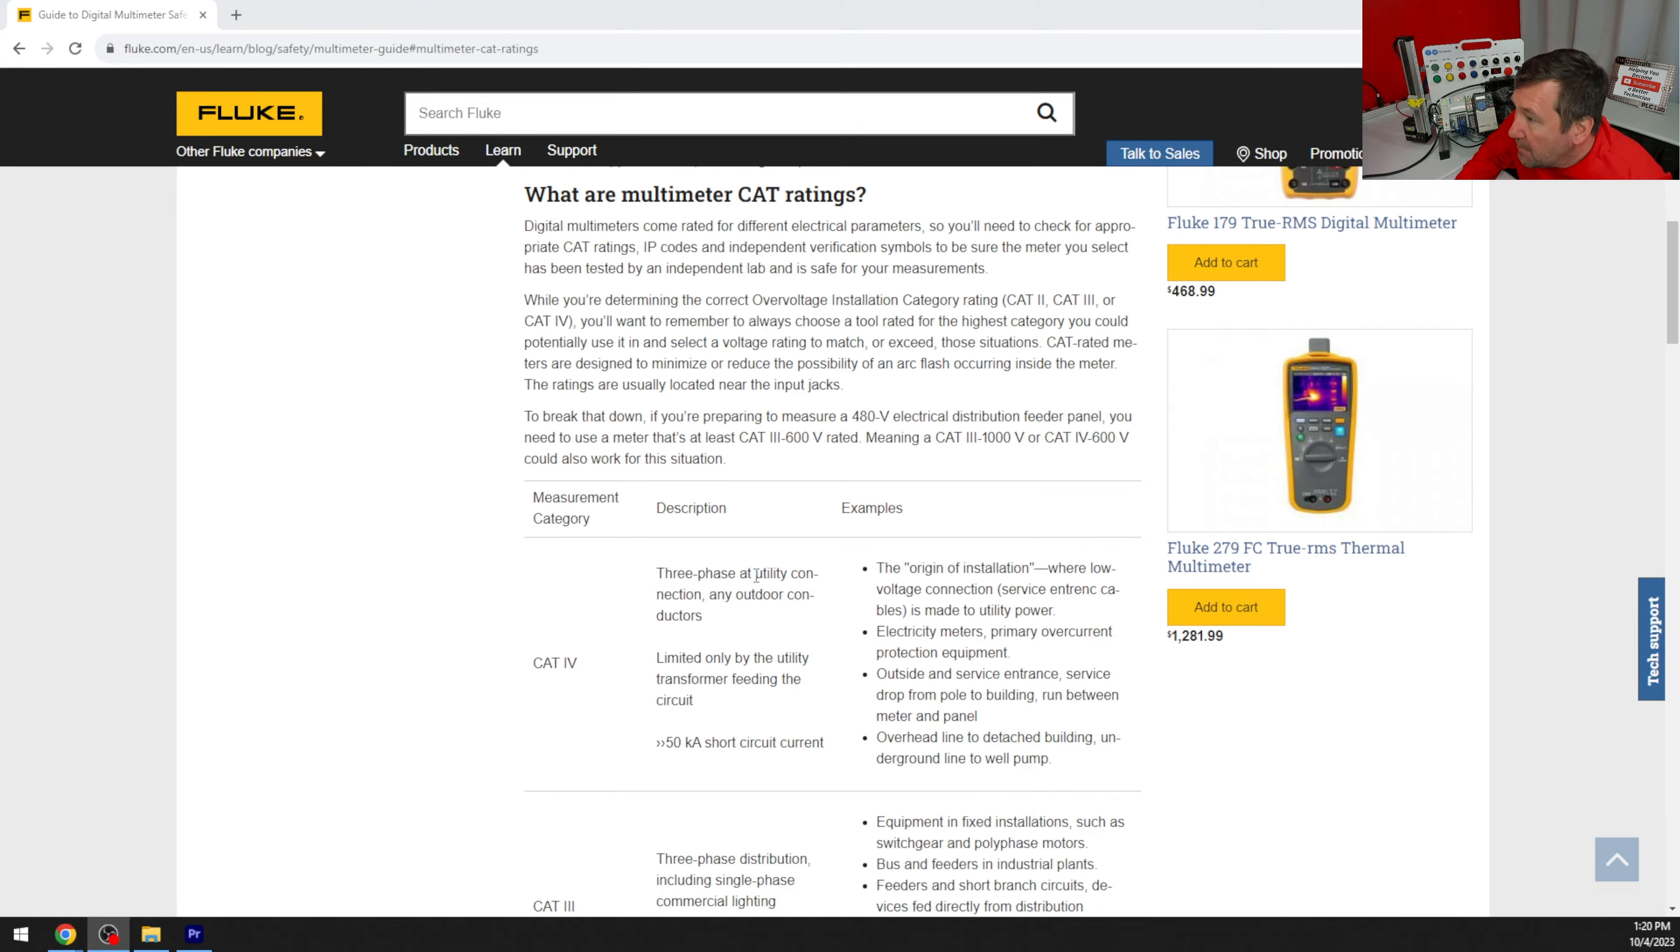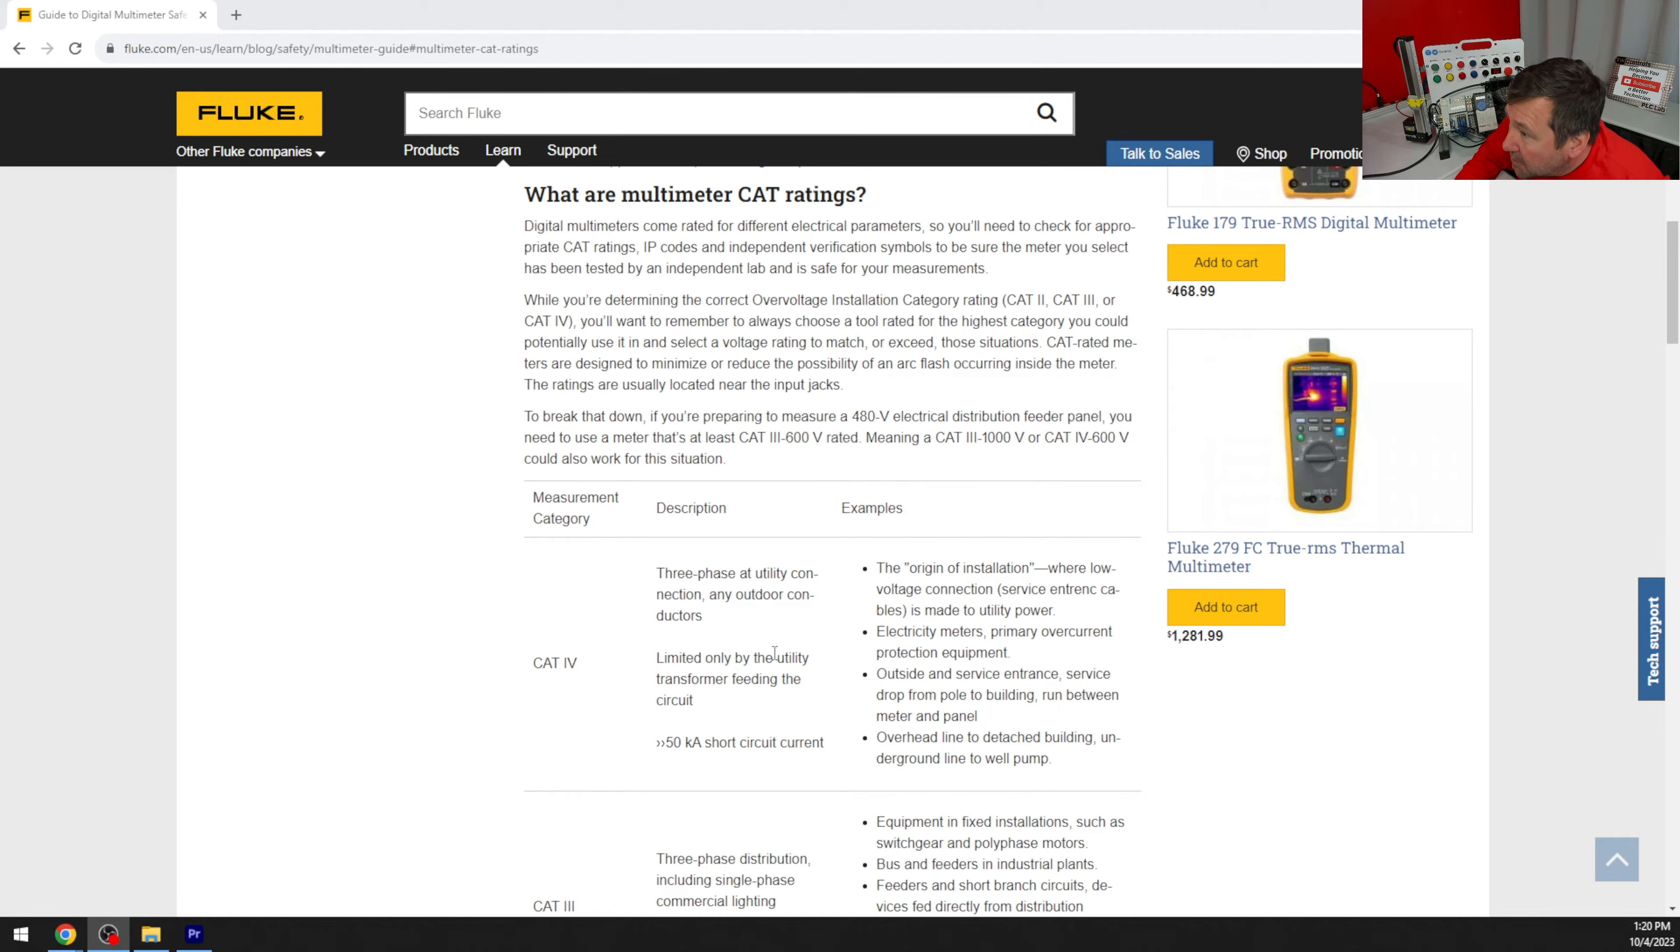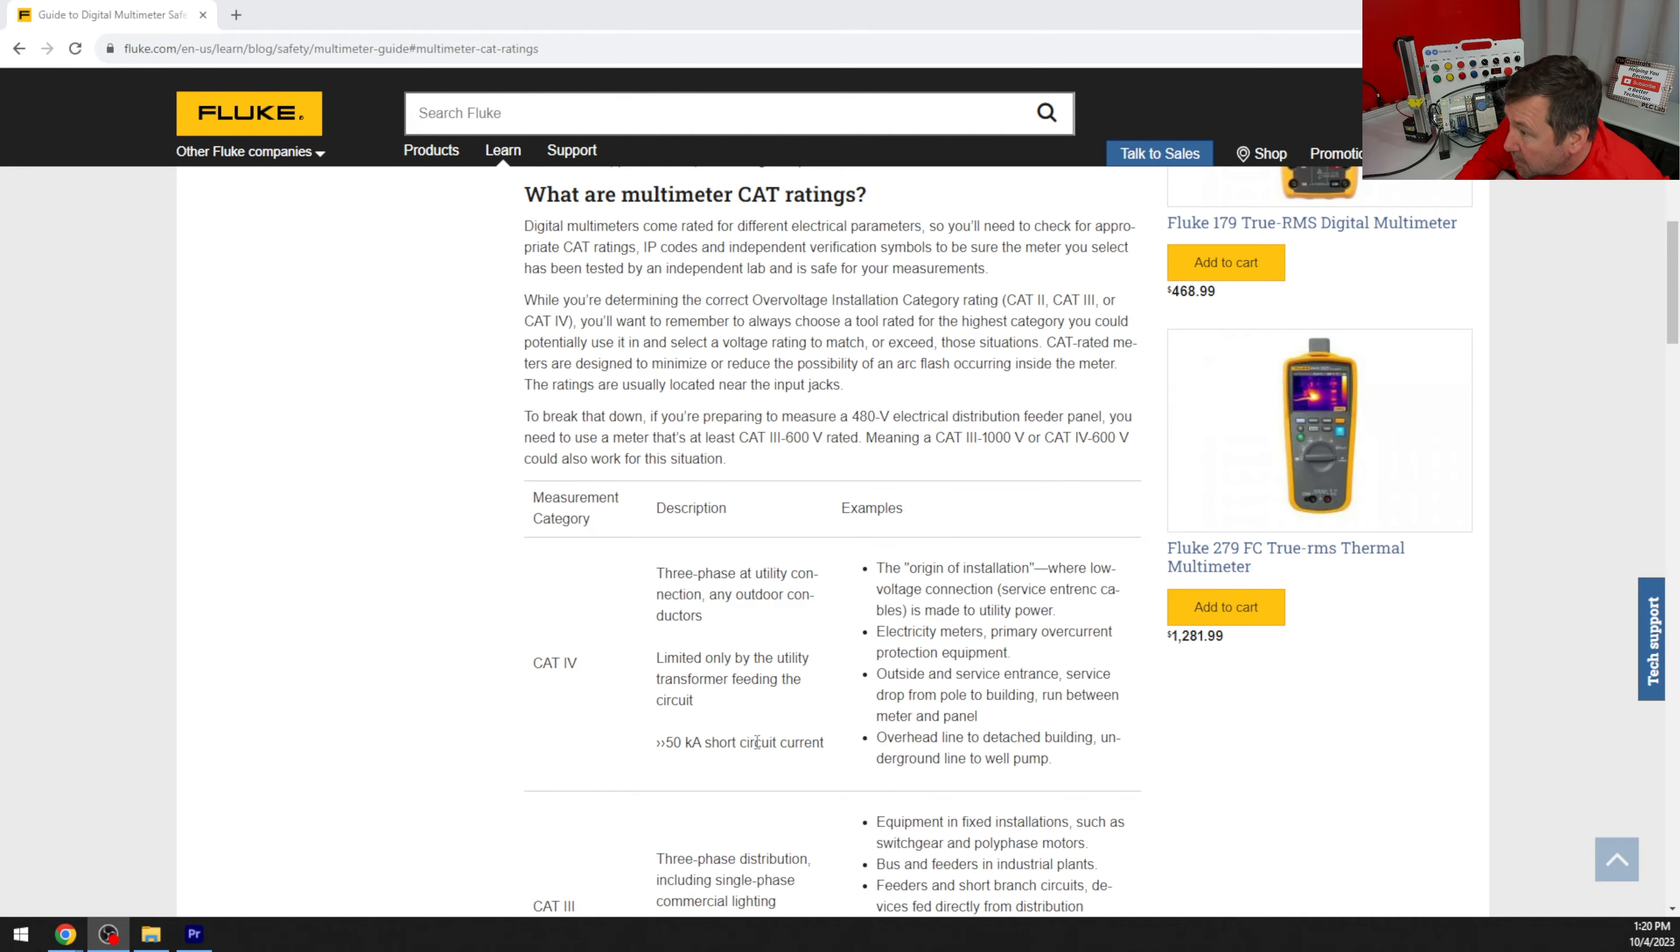So cat 4 is three-phase utility connection or any outdoor conductors, and it's limited by the utility transformer feeding the circuit, and anything greater than 50 kiloamp short circuit current rating.